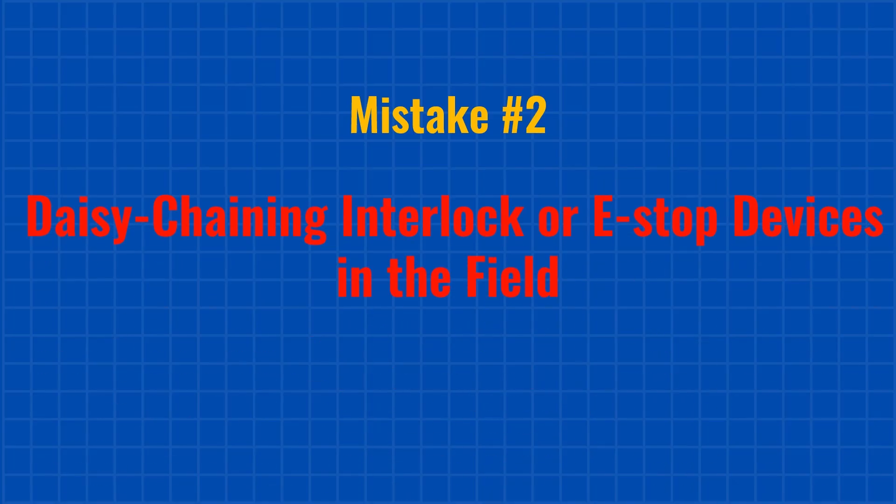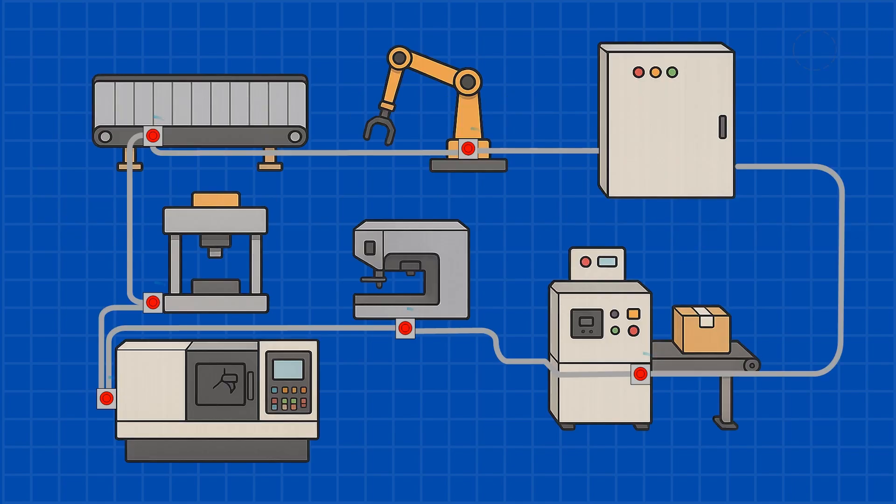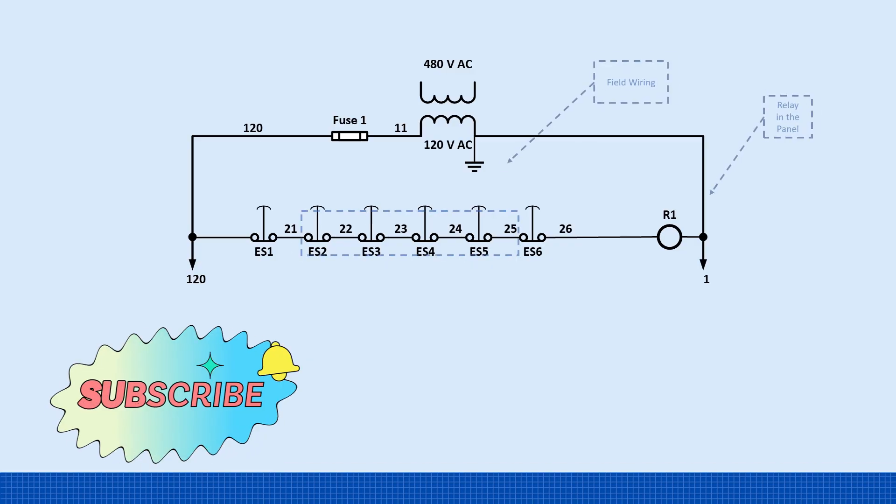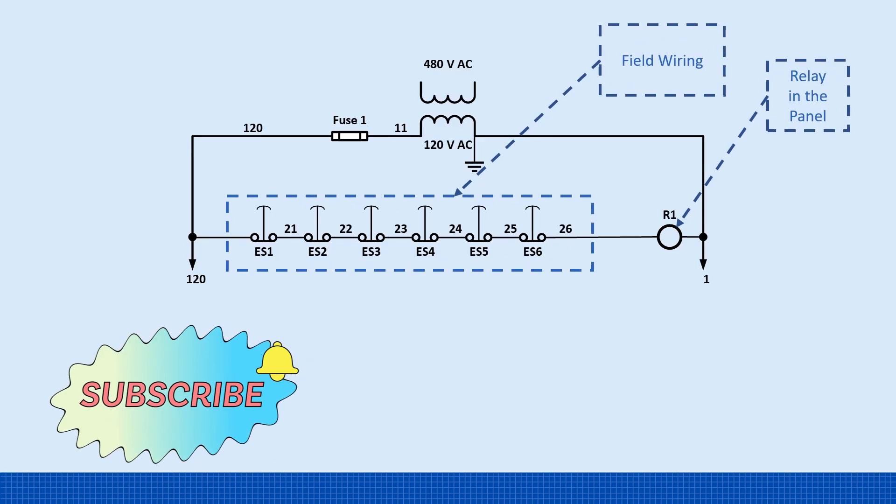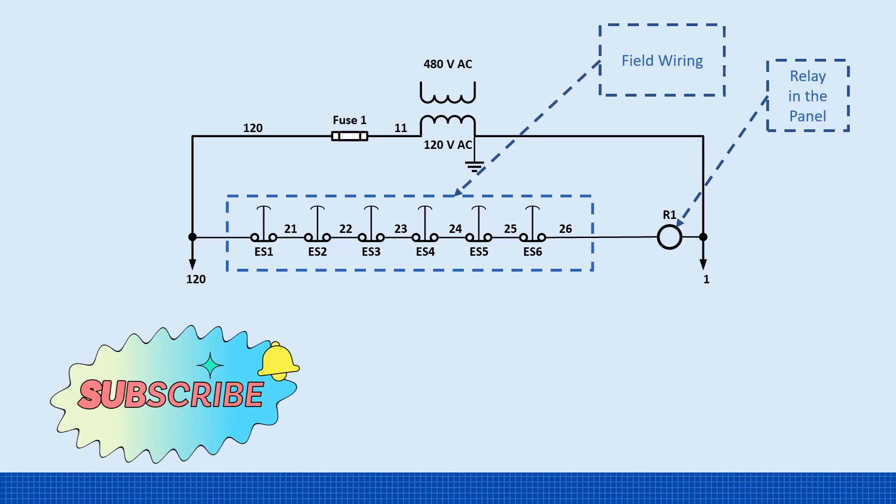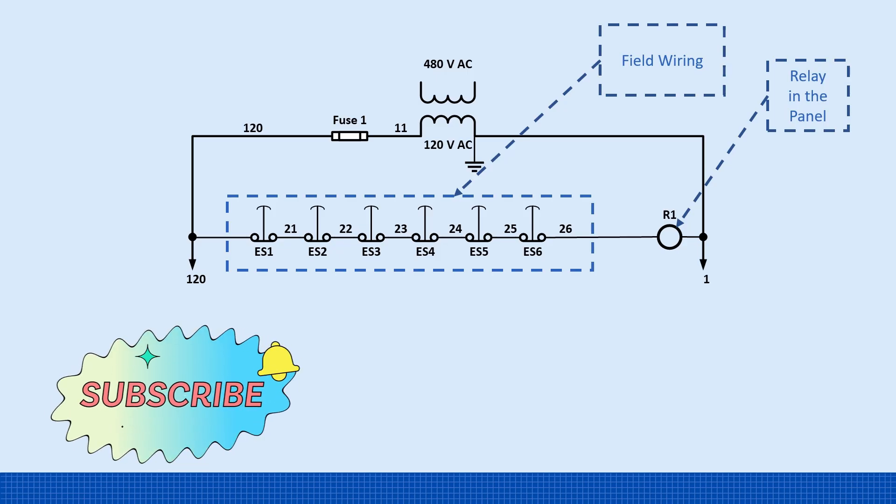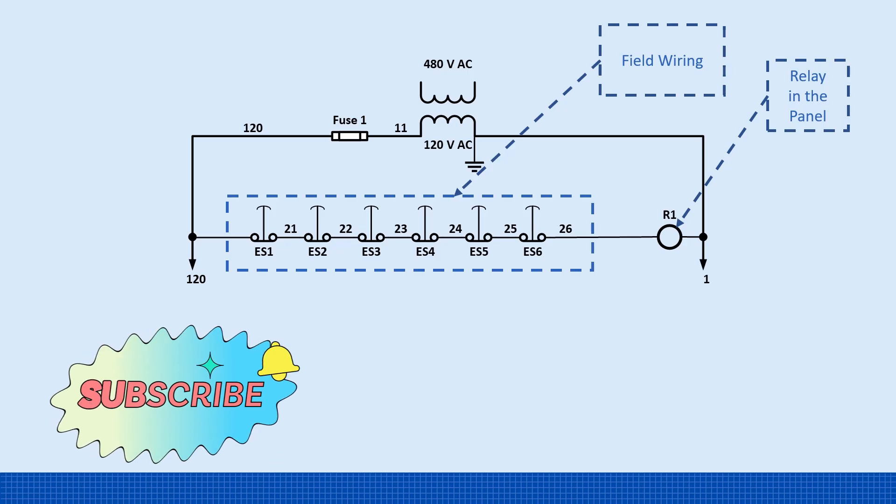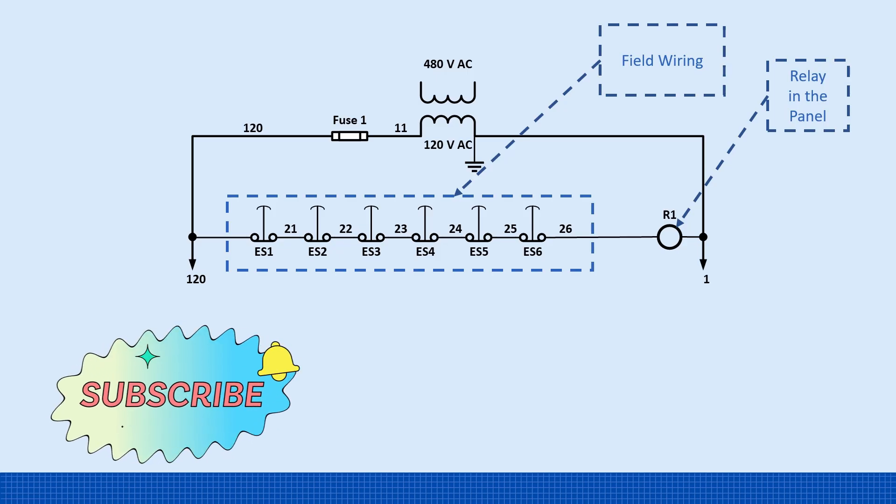Mistake number two. Daisy-chaining interlock or e-stop devices in the field. The real issue with daisy-chaining interlocks and e-stops in the field is troubleshooting. Since only one hot wire goes out to the devices and a single return comes back to the panel, either to a PLC or a relay, any failure breaks the entire chain. That means you have to troubleshoot every device in the field instead of isolating the problem from the control panel.